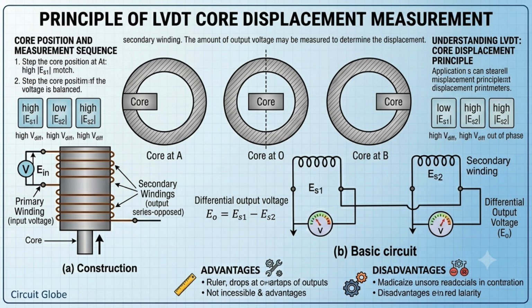Thus, the linear variable differential transformer output voltage is a function of core position. The amount of voltage change in the secondary windings is proportional to the amount of movement of the core. Hence, we have an indication of the amount of linear motion. By noting whether the output voltage is increasing or decreasing, we can determine the direction of motion. Any physical displacement of the core causes the voltage of one secondary winding to increase while simultaneously reducing the voltage in the other secondary winding. The amount of output voltage may be used to determine the displacement.